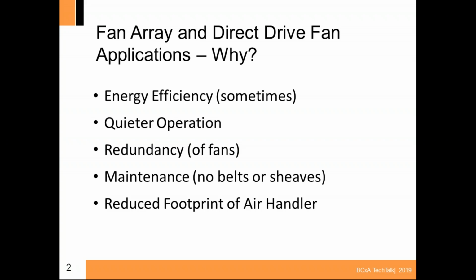So you do get some energy efficiency added out of that, on top of having no maintenance of the belts. That's a big one when they're doing annual maintenance and they've got to check the belt, et cetera, et cetera. The air handlers are typically smaller in size. If you think of a 100 horsepower fan section, how big it is for a single fan, and if you had 9 or 10 horsepower smaller fans, it actually squeezes into a shorter cabinet. Sometimes the cabinet's taller, but it could be a shorter cabinet. But at that kind of CFM, you can imagine how big the coil is.